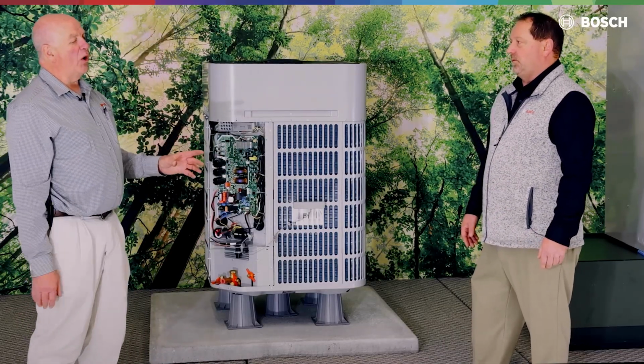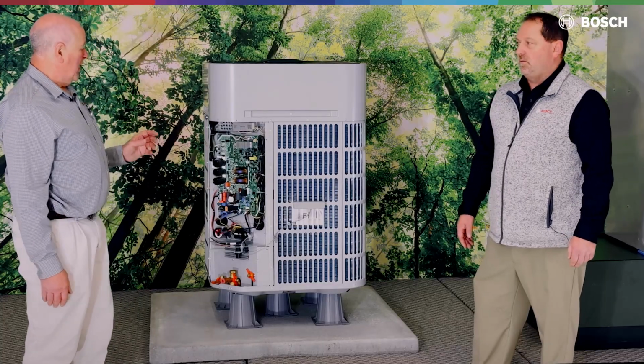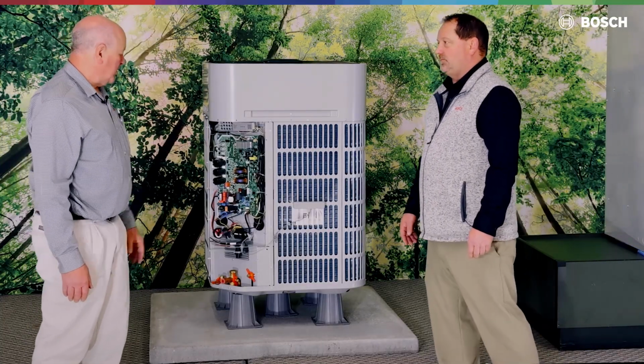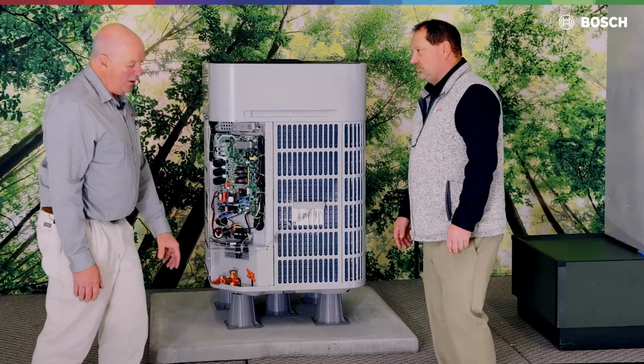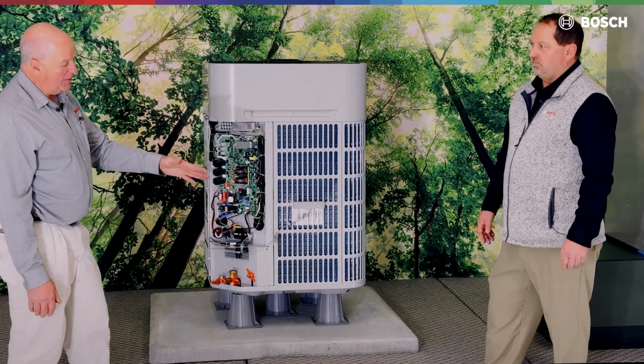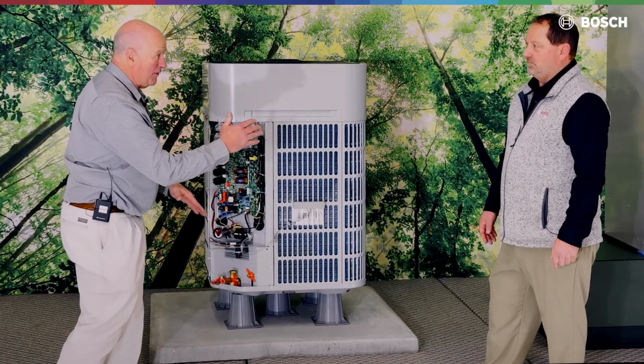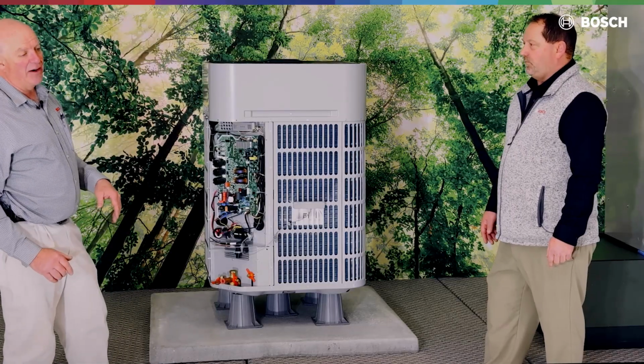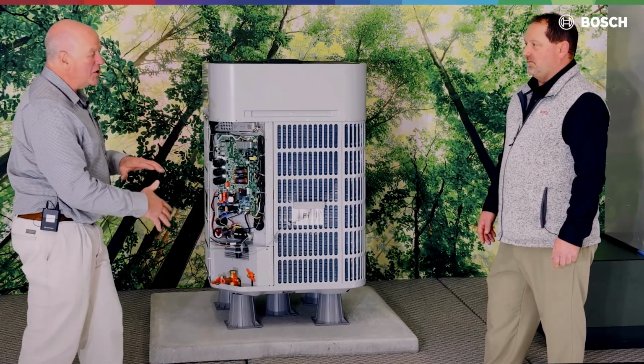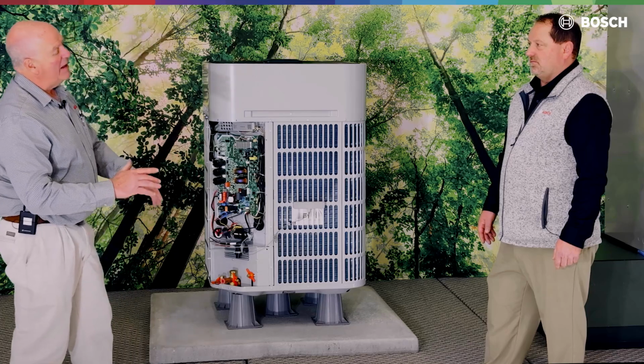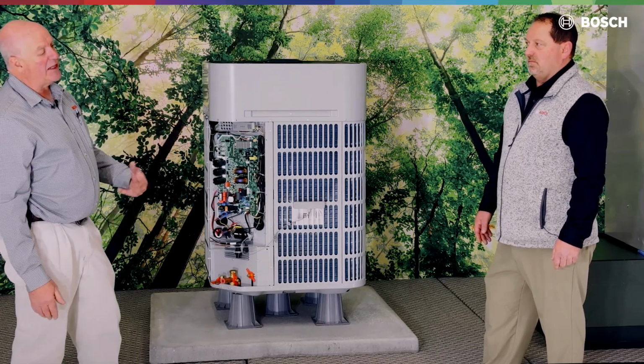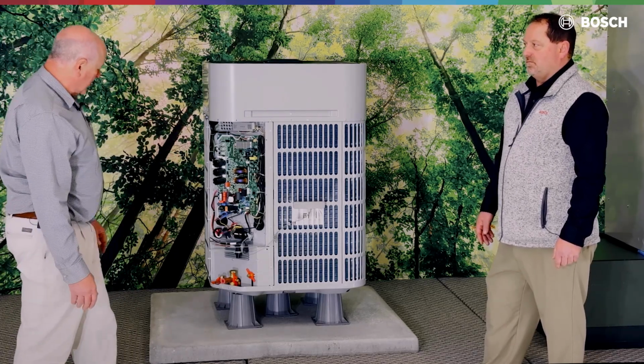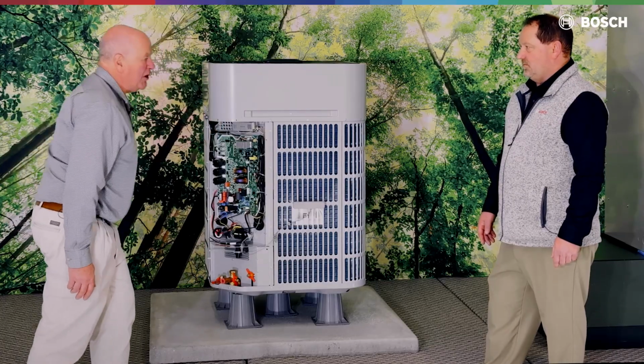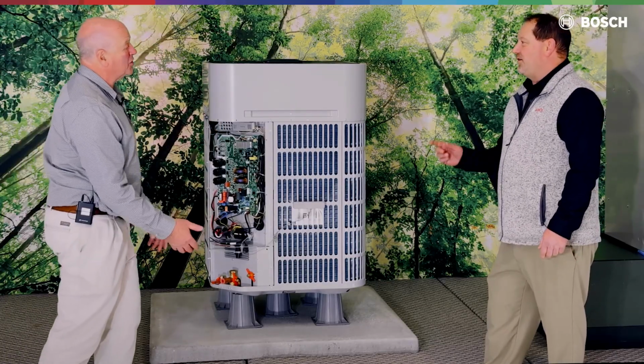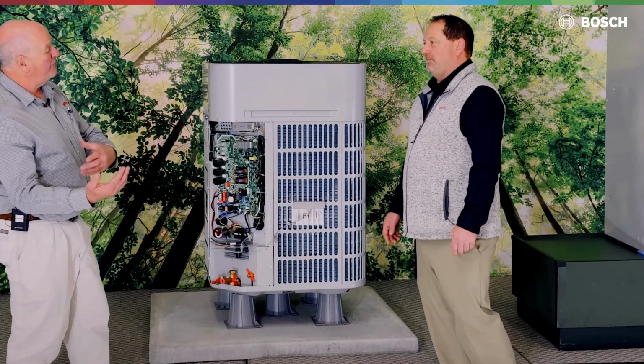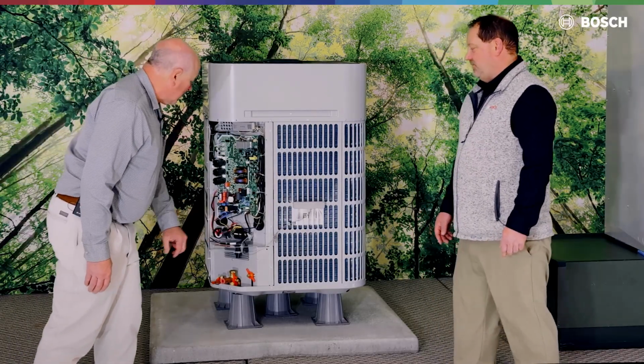Okay. Guys, the whole goal is to get moisture out of the system, and we've got to be very professional about doing that process. So we pull our vacuum, we go back down to our 350 micron. It didn't go above that 350 micron for 1 minute at 500. That's our decay test. If it goes above 500 micron in that first minute, then that means our vacuum's not good or not deep enough. When you pull vacuums in microns, you should be pulling from 2 different locations on that unit. A lot of people like to hook the micron gauge right to the vacuum pump, and you're getting a fake vacuum. So we pull that second vacuum, it's good.